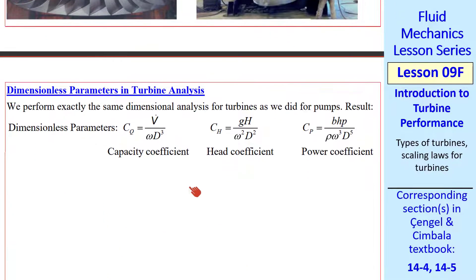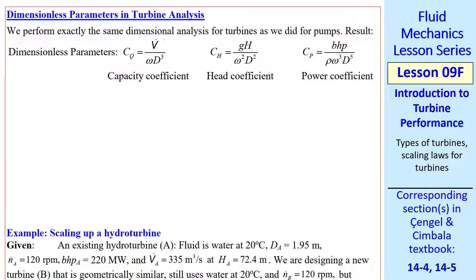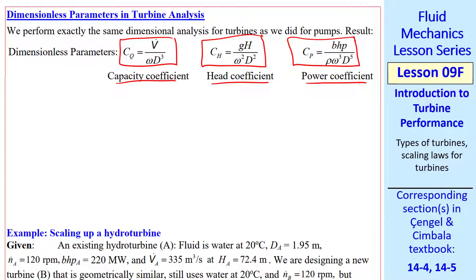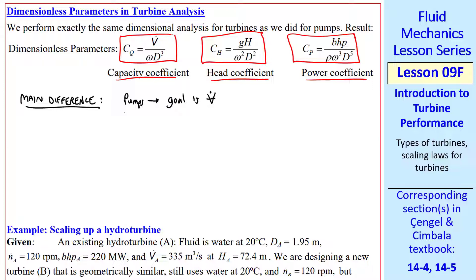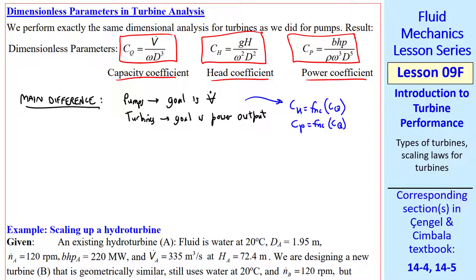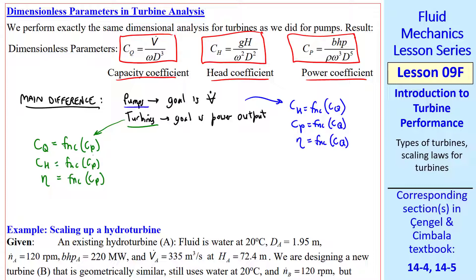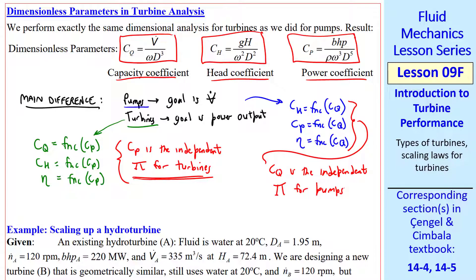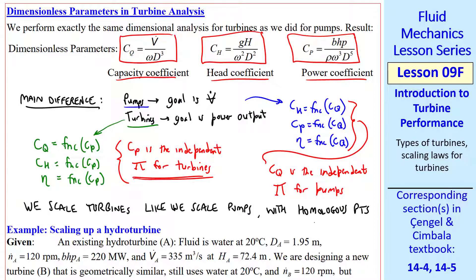Now let's look at dimensional analysis and dimensionless parameters for turbines. The parameters and their names are identical to those for pumps: capacity coefficient CQ, head coefficient CH, and power coefficient CP. The main difference is that for pumps the goal is volume flow rate, whereas for turbines the goal is power output. For pumps, CH = f(CQ), CP = f(CQ), and η = f(CQ). For turbines, since the goal is brake horsepower, we evaluate CQ = f(CP), CH = f(CP), and η = f(CP). In other words, CP is the independent pi for turbines, whereas CQ is the independent pi for pumps. We scale turbines with homologous points, the same procedure except for the change of independent pi.